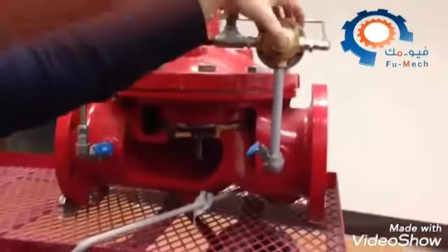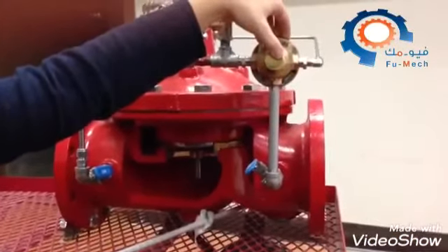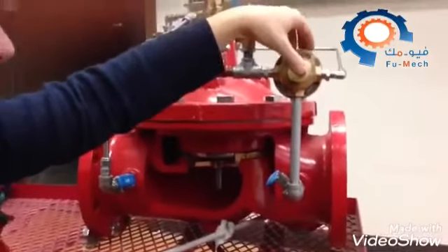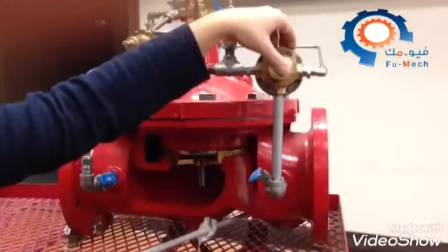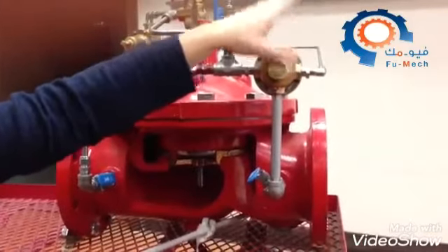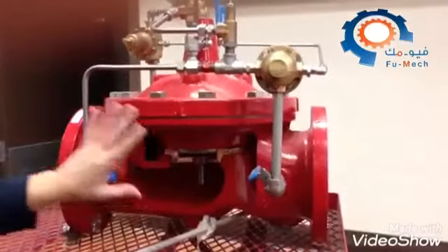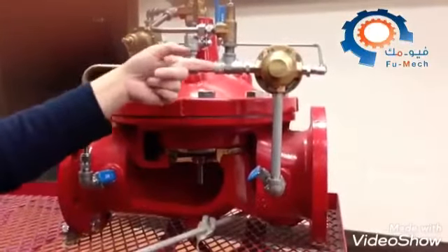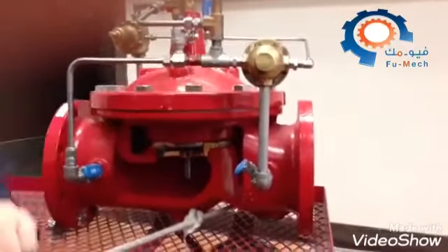So when we talk about a pressure reducing valve like this, this is a reverse seated, normally open valve. Because it fails open. All right. So if this one fails open, what happens in this assembly here? What happens to the water? This is still letting in 0.1 liter per minute. What happens when this fails open?